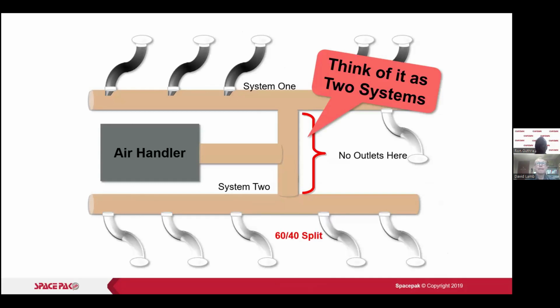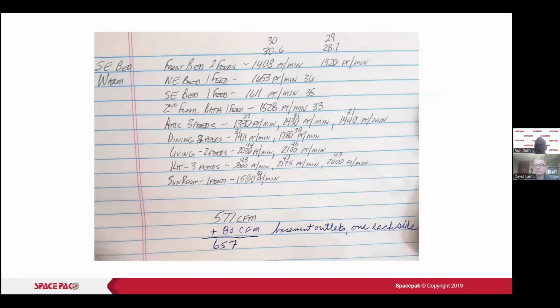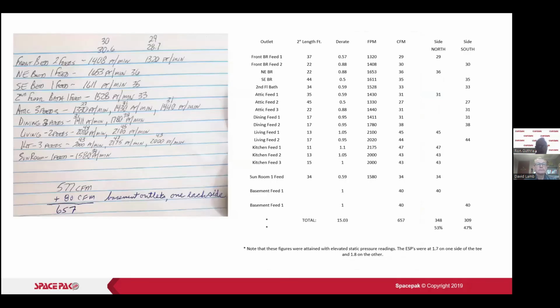For zoning, we can put the zoning dampers in and use sort of an H system, or we do have zoning dampers that will go on each and every one of these runs. I did a shotgun system, and that way I could put my zoning dampers on whichever run was going to what zone that was. Here's an exercise that you need to do, and I have it in the handouts, using a manometer or velometer basically to determine how many CFM you have. It's 0.0218, okay, as the square feet of a 2-inch hole.